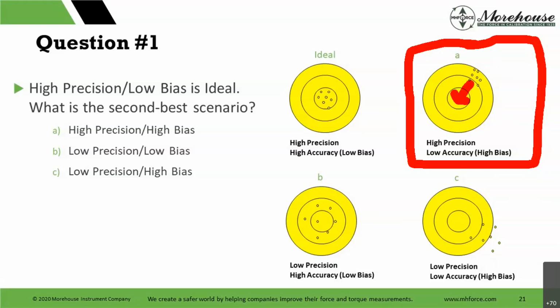Now B is a good answer, but our scatter, our repeatability condition, is worse. So I get it would be ideal because you're not far off, but again, it depends on your tools and your measurements and what you can do and what you can adjust. And if we're going by definitions, the definition of calibration in the VIM does not include adjustments.